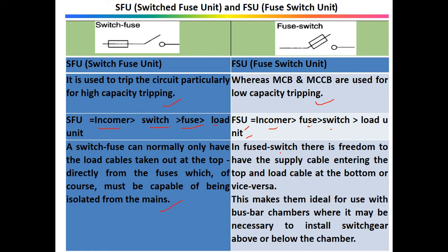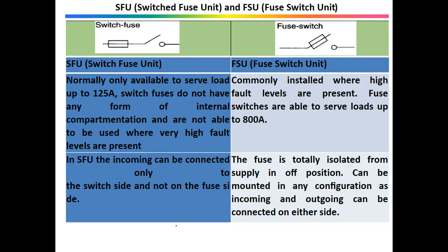It doesn't matter. So you will see that in a fuse switch there is a freedom to have the supply cable entering the top and the load cable at the bottom or vice versa. So this makes them ideal for use with busbar chambers where it may be necessary to install switchgear above or below the chamber. So whenever you are using SFUs, you should always take care that you have to take the cable from the top only. However, in case of FSUs, there is a flexibility that we can take the cable from the downside and the upside, it doesn't matter at all. So accordingly, just by seeing where the wiring is coming, you can say whether it is an SFU or an FSU.